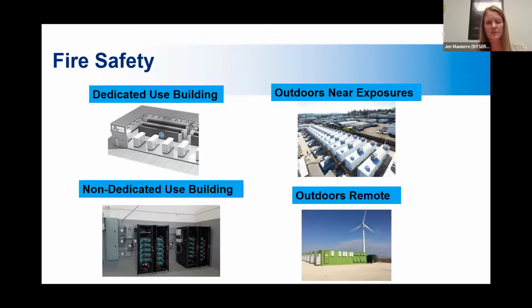Outdoor systems in general are going to have a little bit more leniency than any of the indoor systems, but not outdoors that are near exposures. If they're near another building, within, I think it's 100 feet, of anything that could potentially catch fire, a building, certain types of trees, for example, or fencing, anything like that, it's going to have more strict requirements to meet than an outdoor system that's remotely located and not near anything that's going to catch fire.